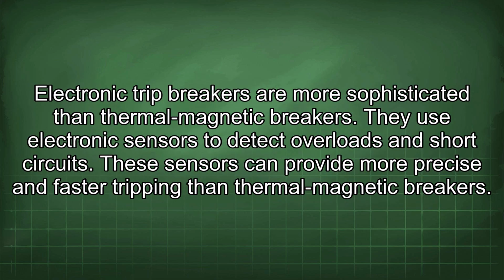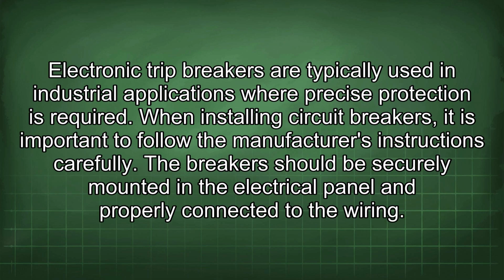Electronic trip breakers are more sophisticated than thermal magnetic breakers. They use electronic sensors to detect overloads and short circuits. These sensors can provide more precise and faster tripping than thermal magnetic breakers. Electronic trip breakers are typically used in industrial applications where precise protection is required.